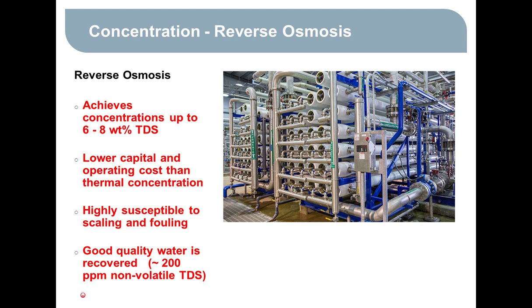For RO, you can get up to 6 to 8% by weight of dissolved solids in the wastewater. So whatever your starting point is, you can get to 60 to 80,000 milligrams per liter of TDS, which is 6 to 8 weight percent. If you get above that, reverse osmosis doesn't work so well anymore because you're getting above some osmotic pressure limits in the RO system. RO is generally the lowest cost option for concentrating wastewater, but the RO membranes are susceptible to scaling and fouling, so you have to be very careful about pre-treatment before you put wastewater through an RO system.